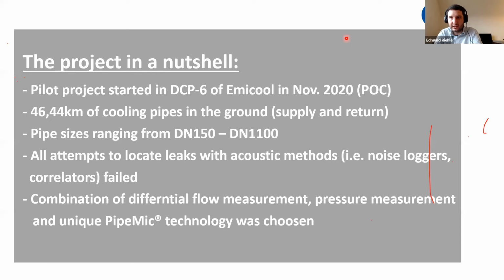I already mentioned the reasons in the beginning. There is a lot of ambient noise you have on the pipe naturally. Therefore, in this project we chose a combination of differential flow measurement, pressure measurement, and our unique PipeMic technology to locate and pinpoint the leaks really precisely in the end.